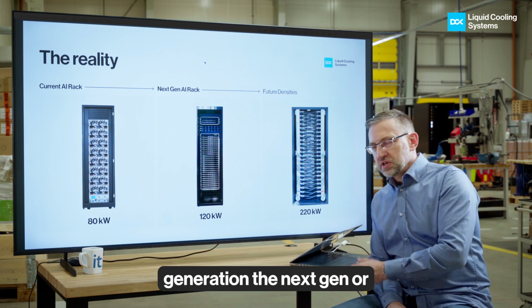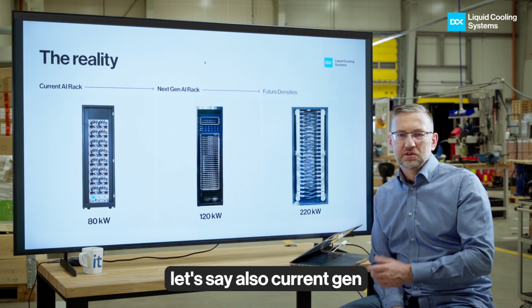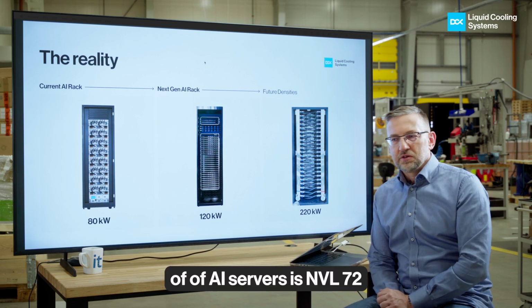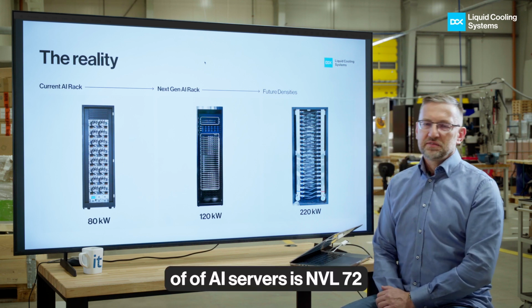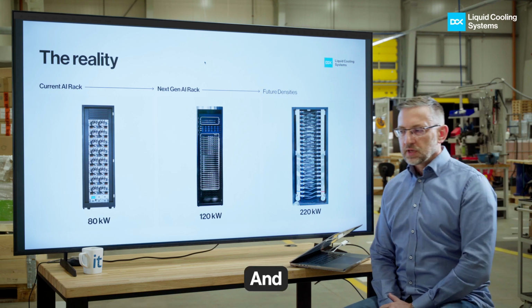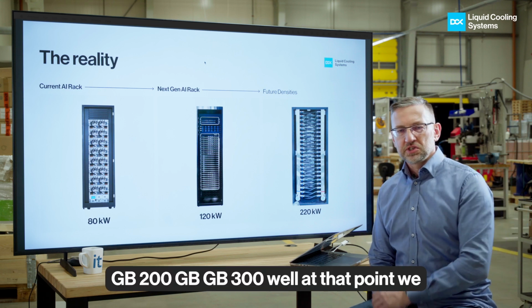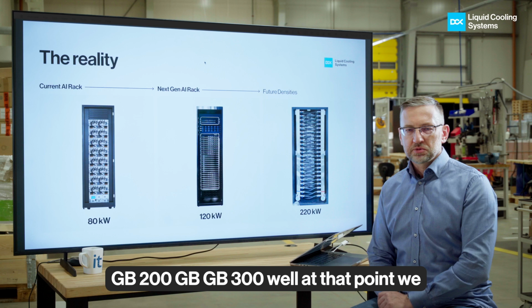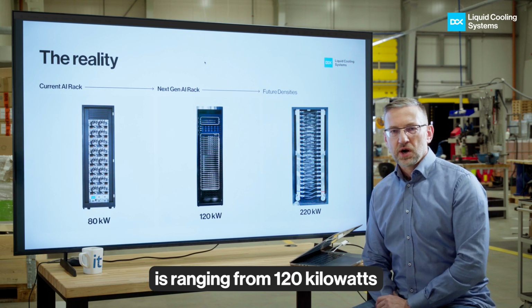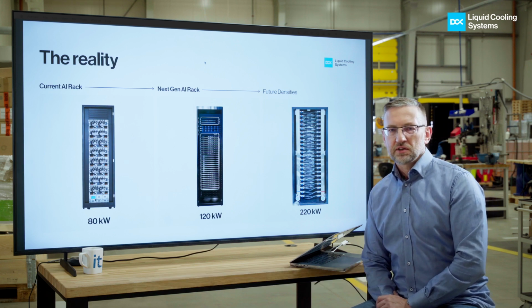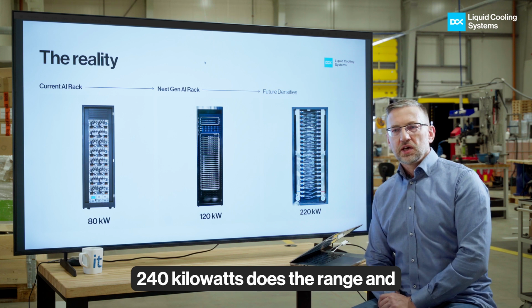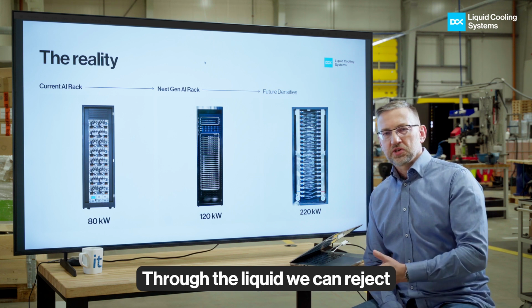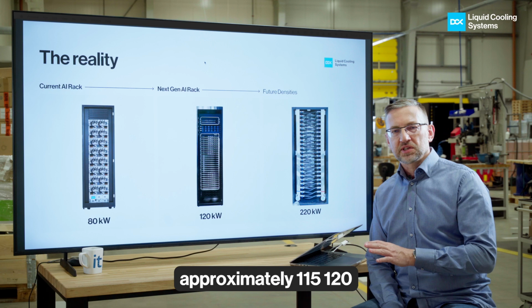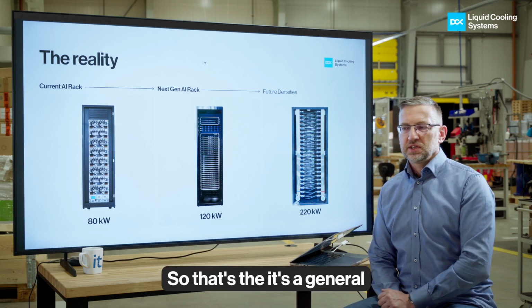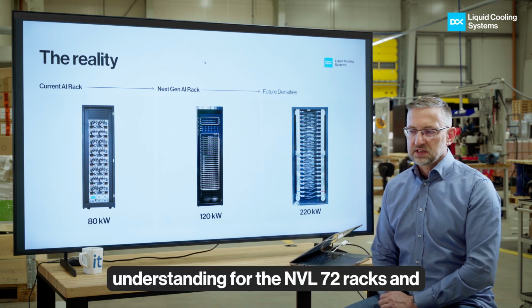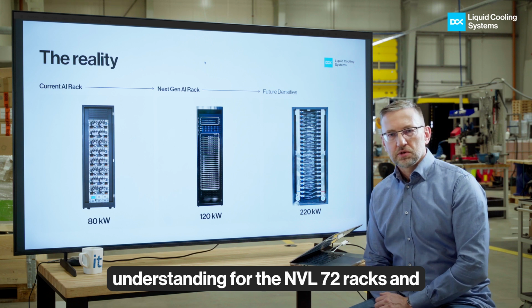The current generation, or let's say also current gen of AI servers is NVL72, GB200, GB300. Well, at that point we are talking about the densities ranging from 120 kilowatts to 140 kilowatts. That's the range. And through the liquid we can reject approximately 115, 120. So that's the, let's say, general understanding for the NVL72 racks.